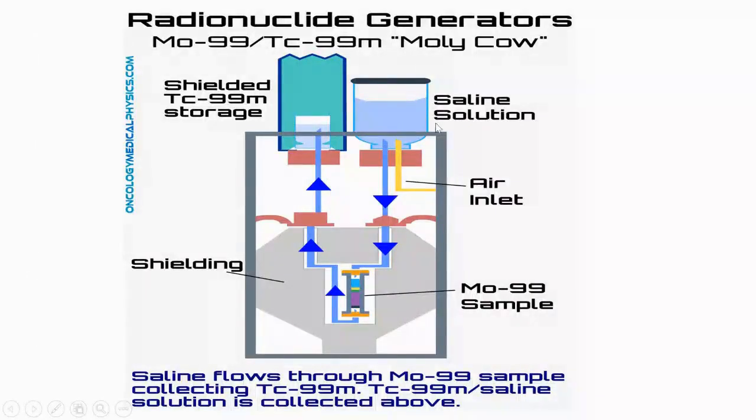If we open the generator from the inside, you'll find it looks like this. First of all, this generator is very heavy, not light. It can weigh around 35 kilograms or so. This is because its outer layer contains lead, which is meant to block any radiation, whether gamma or any other type, and to protect the worker from radiation hazards. Therefore, it must be shielded. The density of lead is high, which makes the generator heavy.